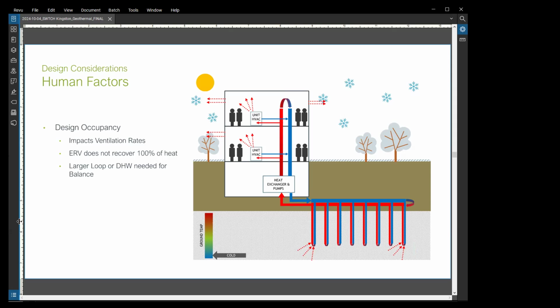If you just take that number straight and apply it to your geothermal field and say we're going to have all the people in the building at all times, and all the exhausts are going to run at the exact same time all day, suddenly your field has exploded in size, and the metrics of making it practical to install become tricky. So you have discussions back and forth with your design team: are we comfortable with this assumption? Are we comfortable saying people really only run their dryer once a week? You kind of thread the needle and balance to bring those occupant assumptions down, because the occupancy assumptions affect your air change requirements.